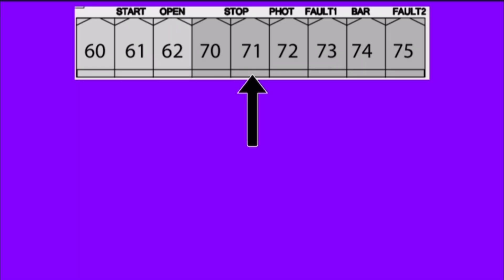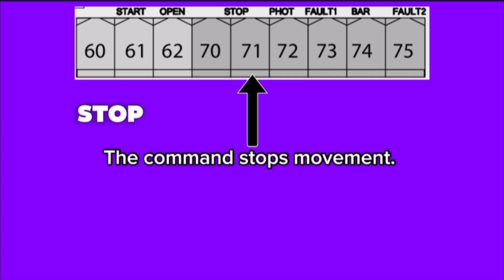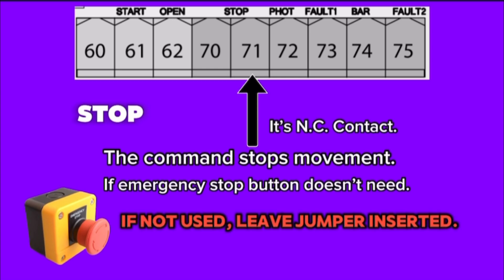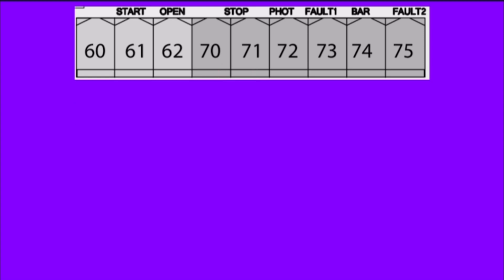Pin 71, stop block. The command stops movement. It's NC contact. If emergency stop button doesn't needed, and not used, leave jumper inserted. Pin 70 and 74 also keep jumper.